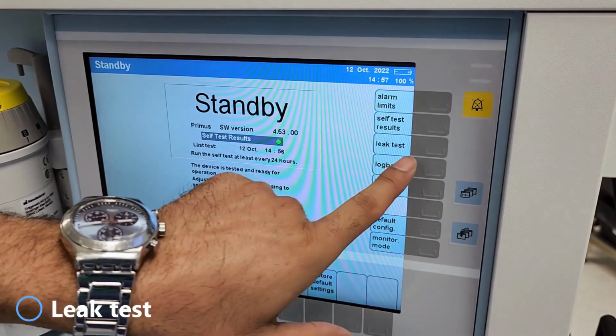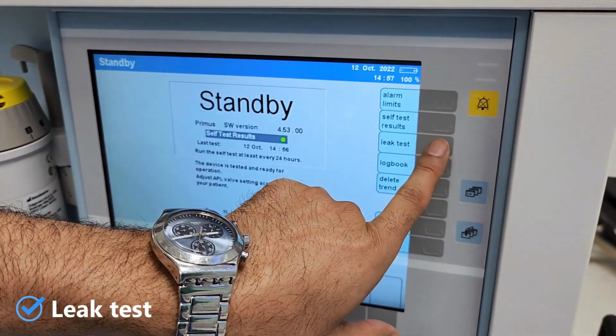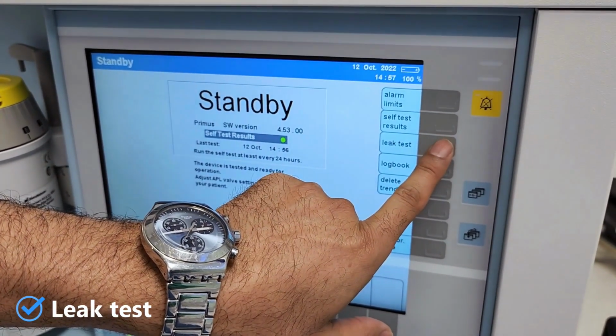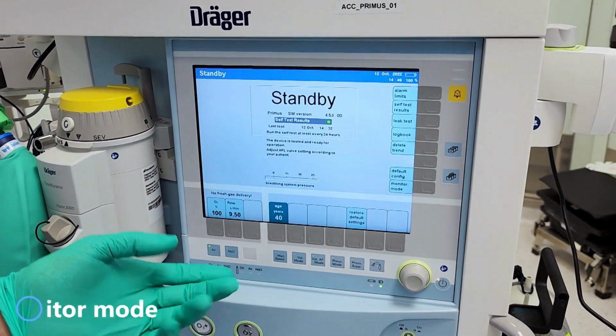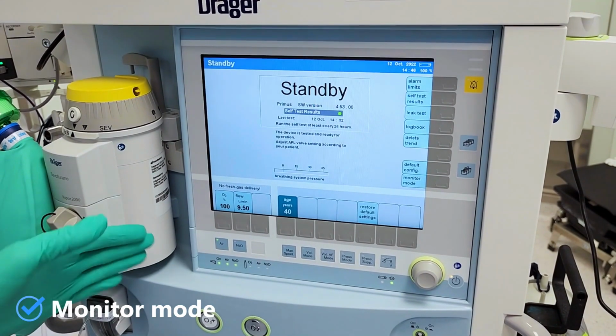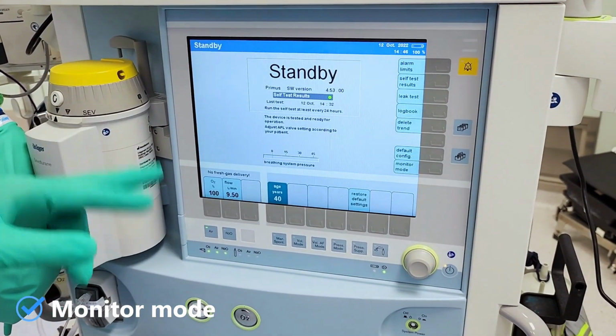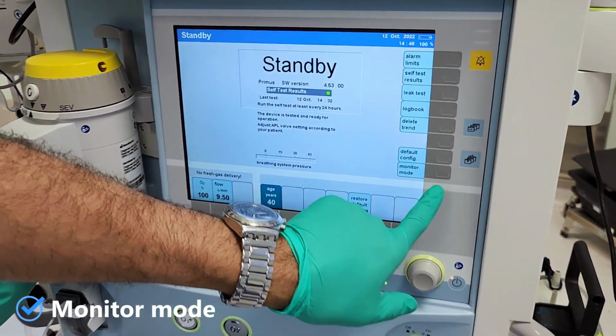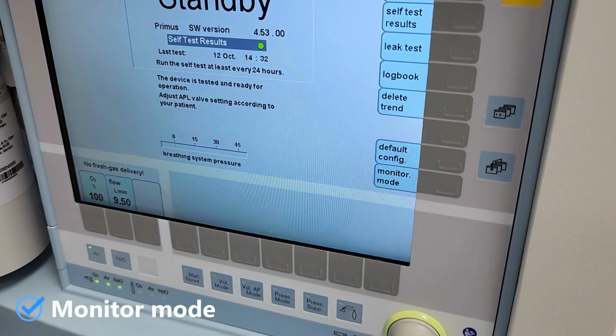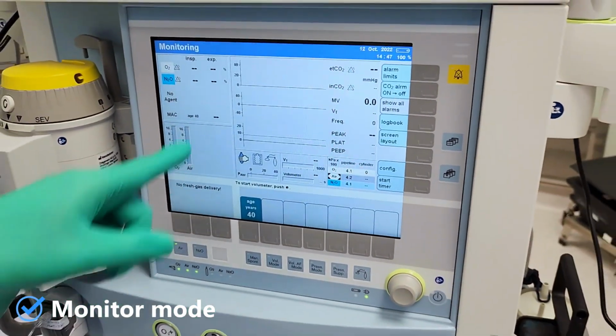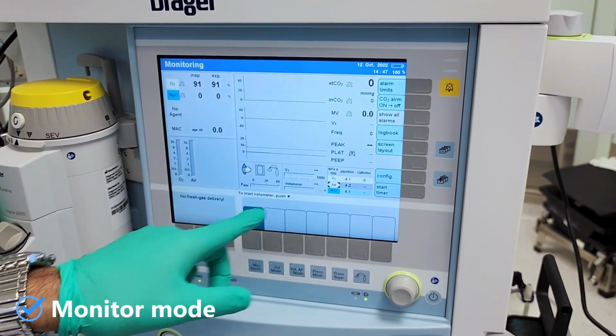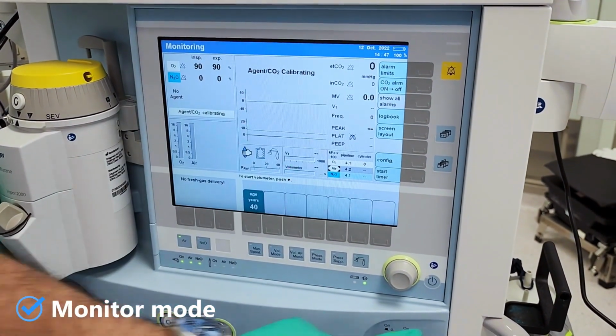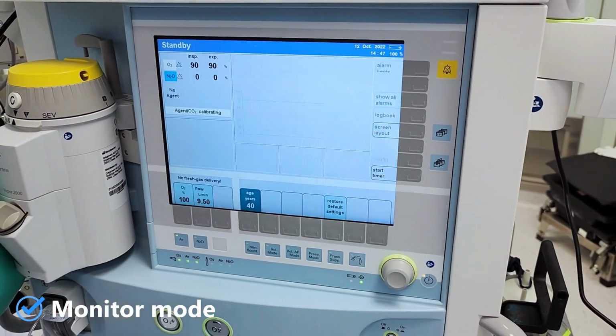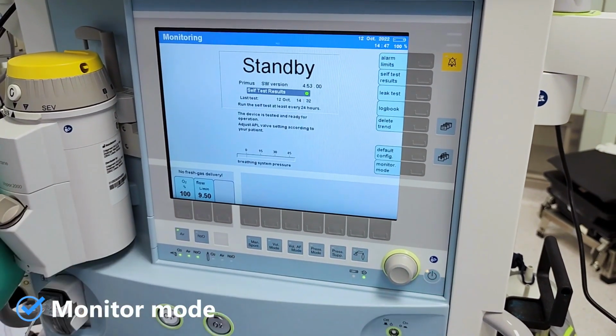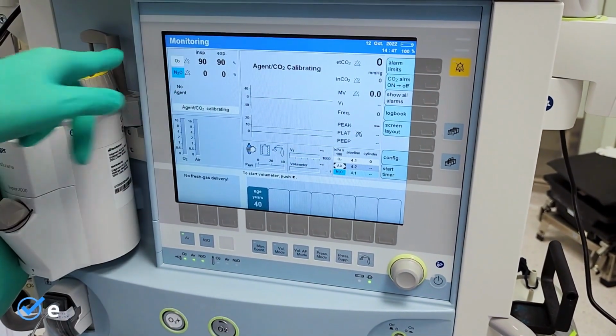A leak test can be performed between cases, when you change the filter, circuit, or soda lime. The test takes around 4 minutes to finish. To put the machine in monitor mode, just to monitor the capnograph, we have 2 ways to do it. You can go from here. Just press the monitor mode, and now we can use it as a capnograph monitor. No gas delivery at all. The other way to do it is to press the power button once, and we are now in monitor mode.